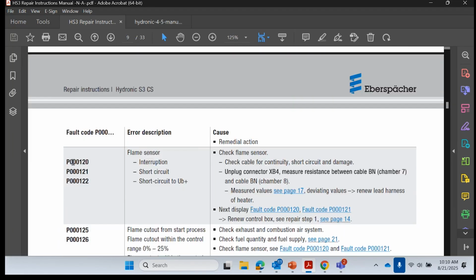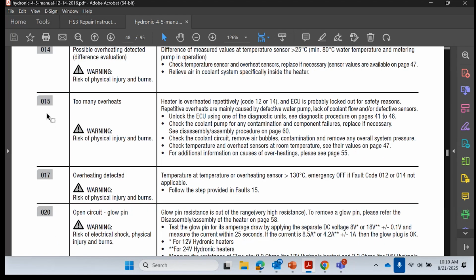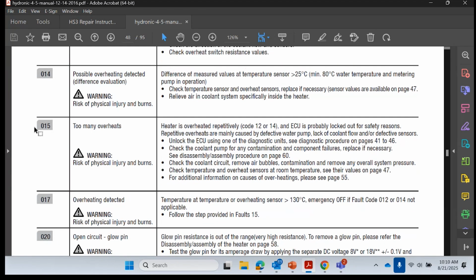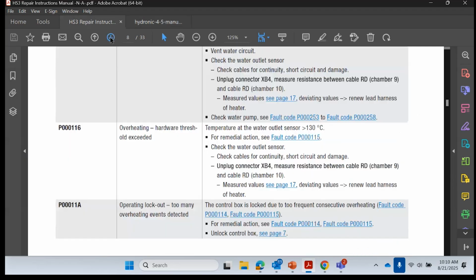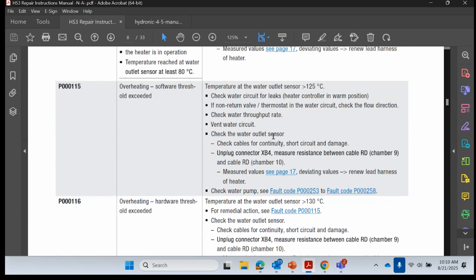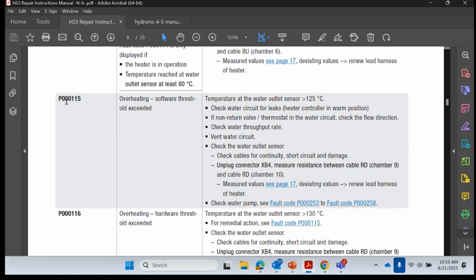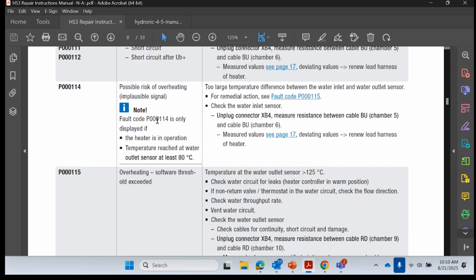Once again, although the format has changed, the description and the instructions to diagnose and repair the issue are very similar. Here we have code number 14 and 15. These are for overheating, for example. Code number 17 is for overheating. This is on the first generation. And if you look at very similar codes, you can see over here, these are the overheating codes. So we have P000115, for example, for overheating, 116 for overheating, etc. So the format has changed, but everything else is still kind of the same.